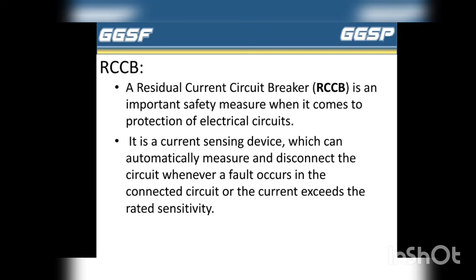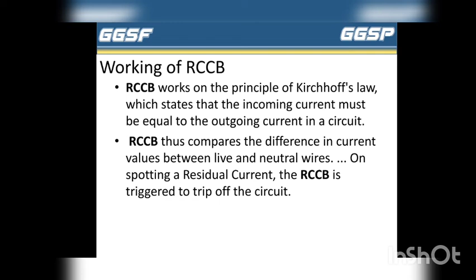Working of RCCB. First, RCCB works on the principle of Kirchhoff's law, which states that the incoming current must be equal to the outgoing current in a circuit. RCCB thus compares the difference in current value between live and neutral wire. On spotting a residual current, the RCCB is triggered to trip off the circuit.